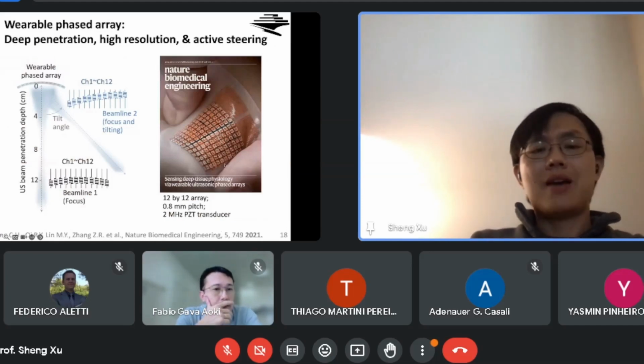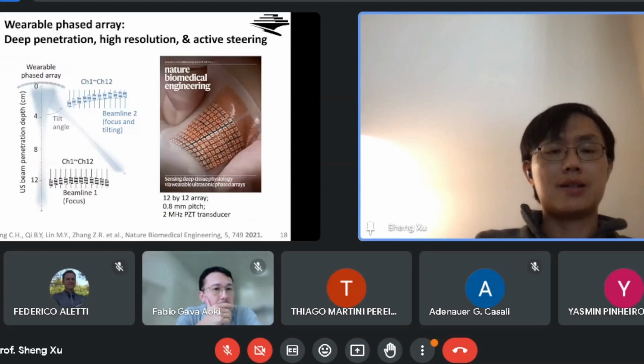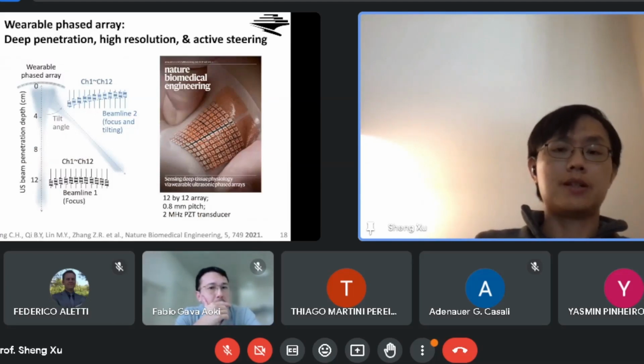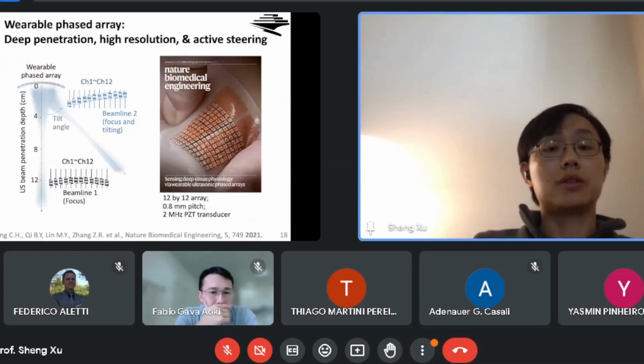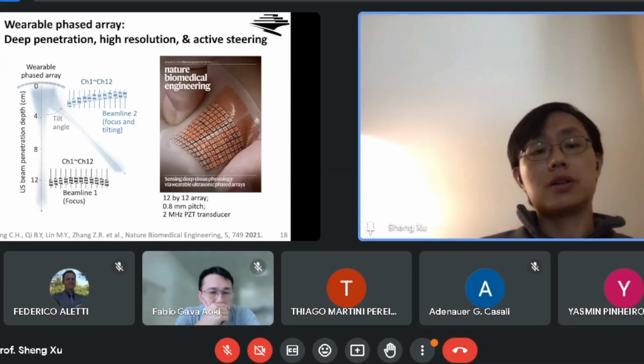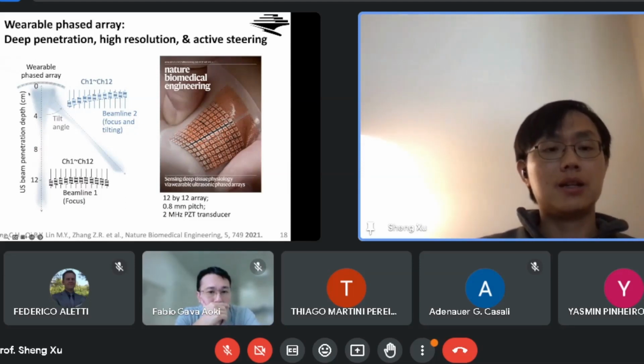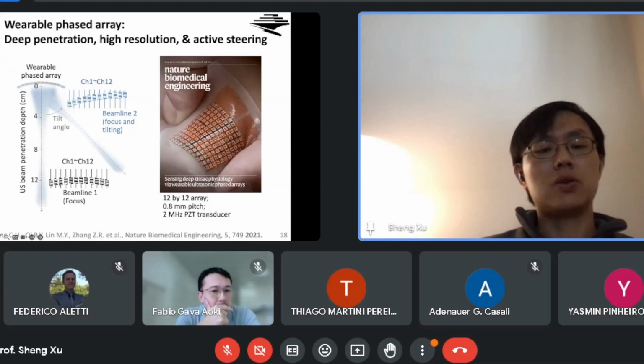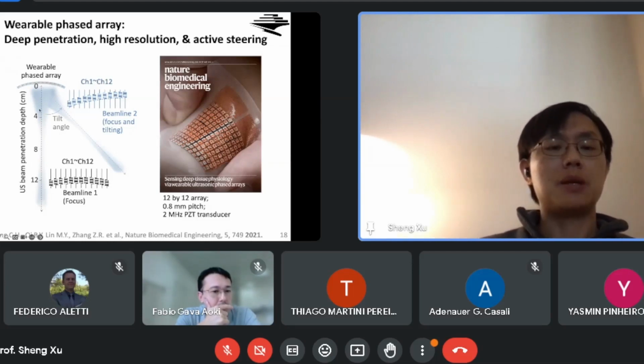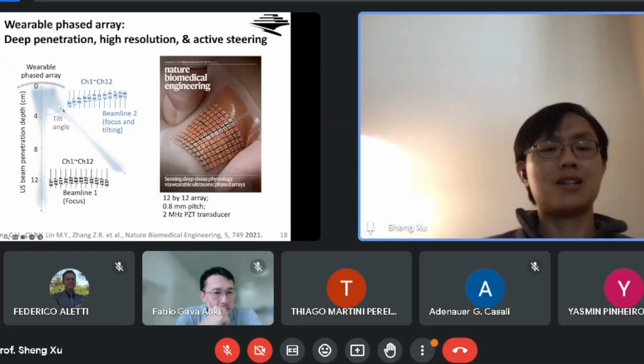So ultrasound is a platform technology, and it has many powerful capabilities. One powerful capability is the so-called phased array. If you do not know what a phased array is, it's basically a technique where, by controlling the timing of activating those transducer elements, the ultrasound beam can be focused and steered to an angle. For example, if you activate all those transducers simultaneously, then the beam will be focused directly beneath the device. If you activate this one first and this one last, then the ultrasound beam will be focused and steered somewhat to the right, right?